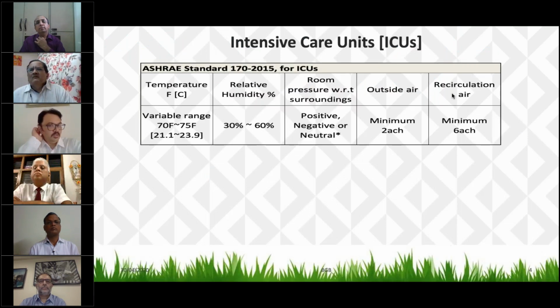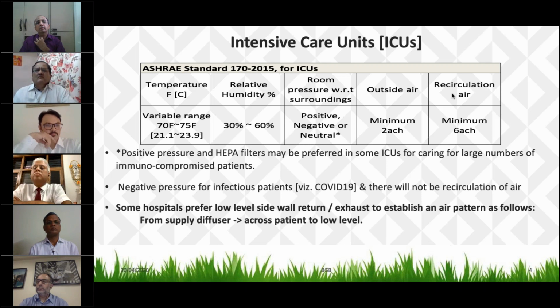Next slide. Yeah, we talk of intensive care units. There is a particular temperature that is accepted, that is 21 to 23.9 degrees, as per ASHRAE. The relative humidity is 30 to 60%, and now in the COVID format we are talking of 40 to 70% for various reasons. And normally it should be positive, negative, or neutral depending on the type of patients that are going to be there. Outside air has to be a minimum of 2 ACPH, that is 2 air changes per hour, and the minimum recirculation of air has to be 6 air changes per hour.